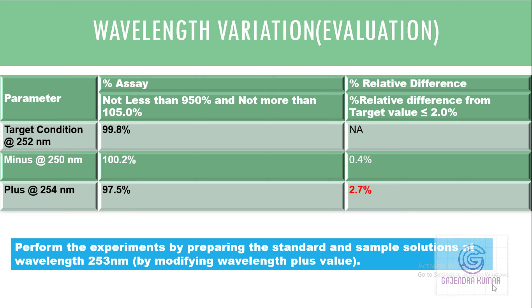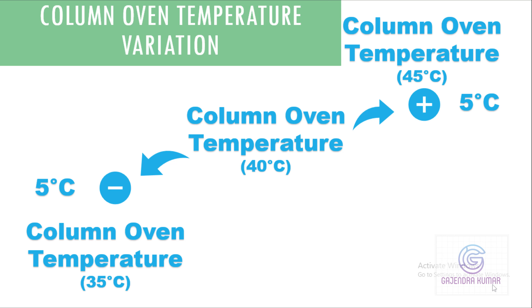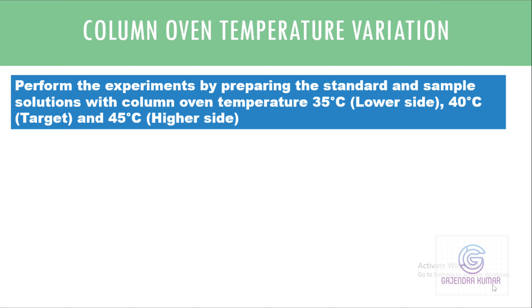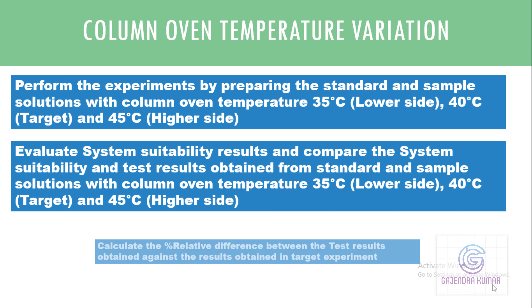Move to the column oven temperature. As per our test method, it is 40, plus 5 degrees, that is 45. Similarly in the lower range, minus 5 degrees, that is 35 degrees. So perform the experiment in a similar manner, as you did for the other parameters. Then evaluate the system suitability results and test results, and calculate the percentage relative difference.